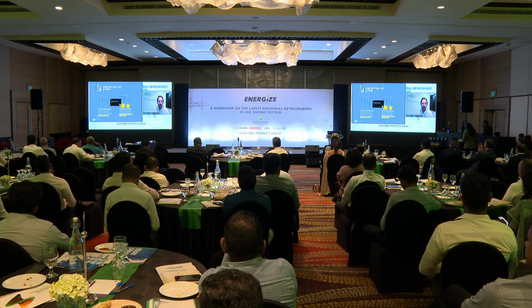Another aspect of polymer insulators that I was alluding to is because you can provide greater leakage distance over a given section length, you also have the opportunity to optimize a line design. So you're able to reduce perhaps the phase spacing or perhaps the tower height because you can target a specific length of a polymer insulator that gives you.